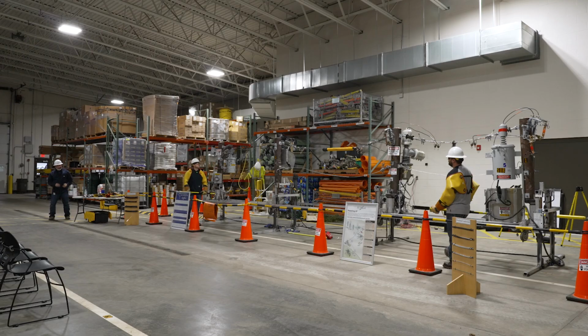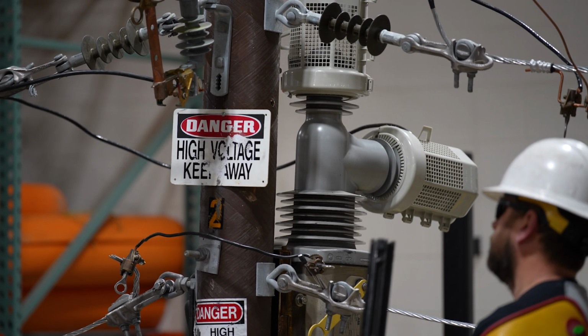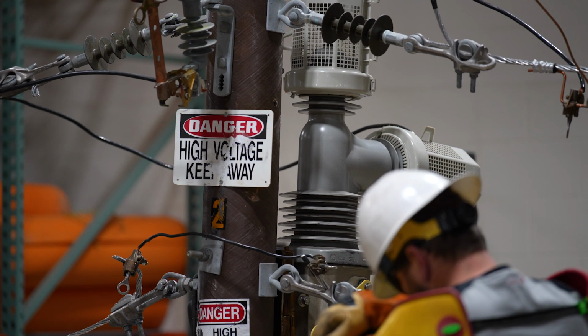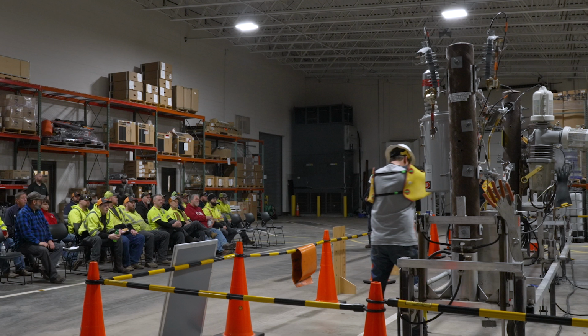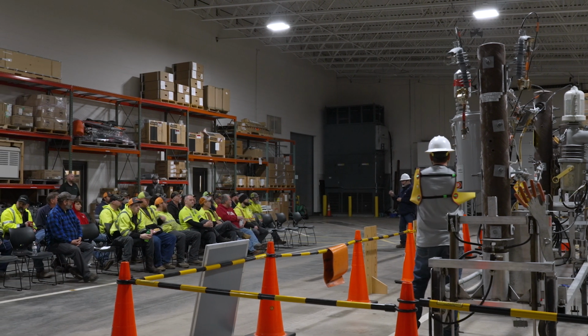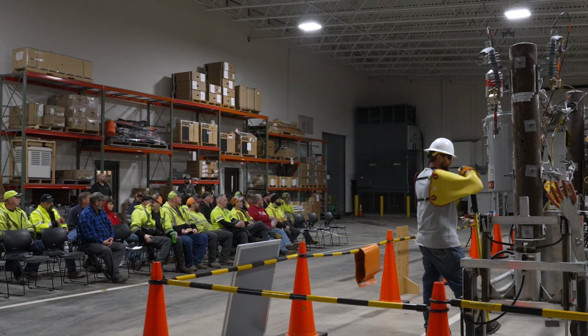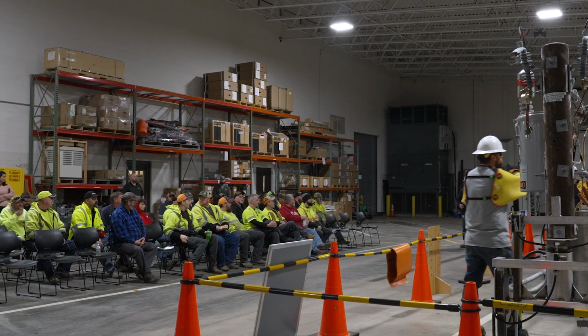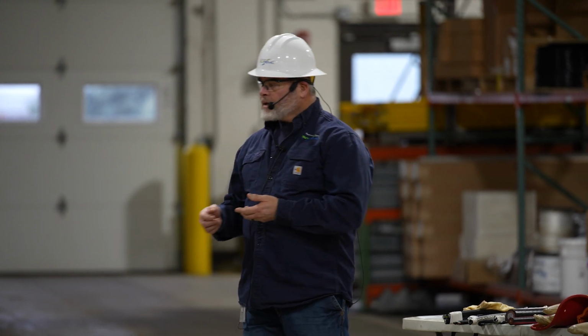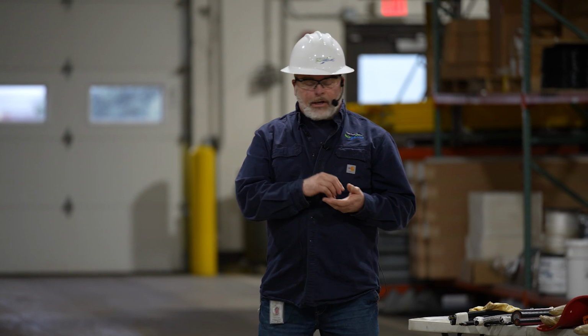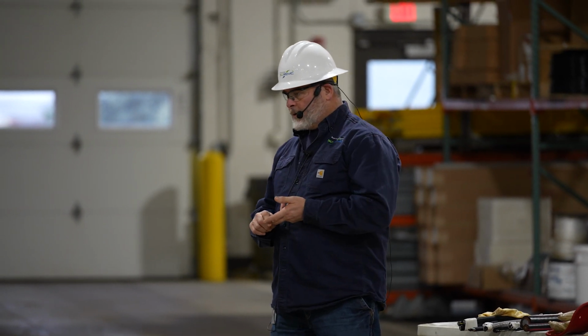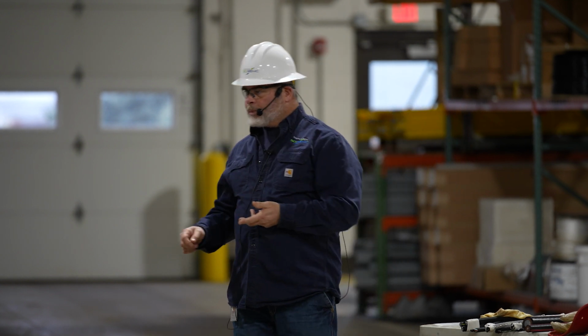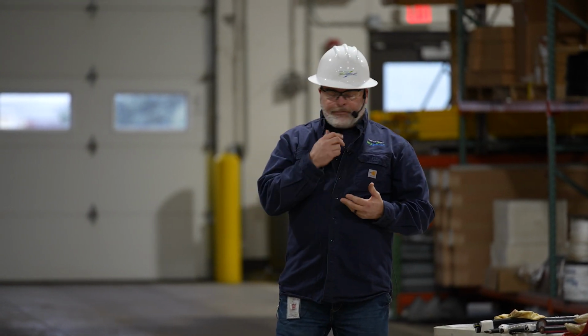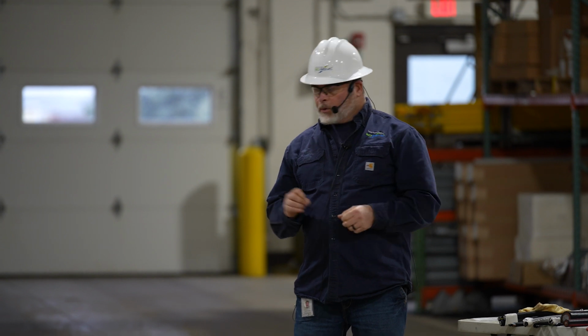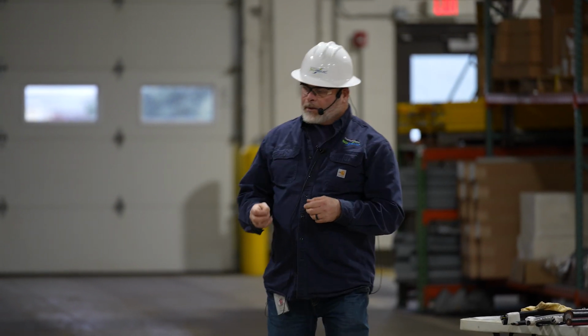Now on down, right here, we have what's called an ECR. It's an electronic circuit recloser. It takes 4 shots before it locks out. We've got a couple fast shots, so instantaneous, it'll trip and come back on, and hopefully the fault has cleared itself already. Then it'll go into 2 longer curves that are called burn curves. If there's a tree on it, it'll try to burn that tree off. Or if there's a squirrel hung up, it's going to try to burn it off on the next 2 shots. If it doesn't clear itself, or the line actually burns down, that's when that unit will go out on its 4th shot and lock out. It'll de-energize the line.